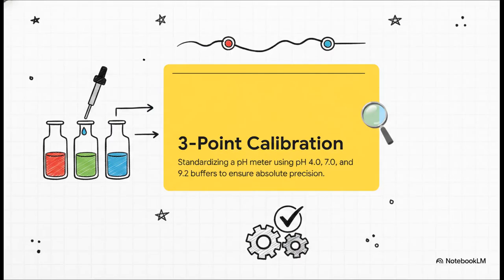Okay, before we even touch a single piece of equipment, we need to understand what a 3-point calibration actually is. Essentially, it means standardizing a digital pH meter using 3 very specific buffer solutions: pH 7.0, 4.0, and 9.2. By testing our meter against a neutral, an acidic, and a basic standard, we're basically proving its accuracy across the entire spectrum. This is exactly what guarantees that our actual sample measurement at the end will be completely trustworthy.